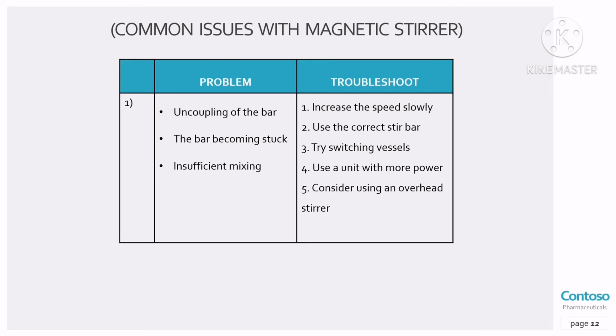Common issue with magnetic stirrer. The problem is uncoupling of the bar becoming stuck, insufficient mixing. So, you must increase the speed slowly. Use the correct stir bar. 3. Try switching vessel. 4. Use a unit with more power. And 5. Consider using an overhead stirrer.